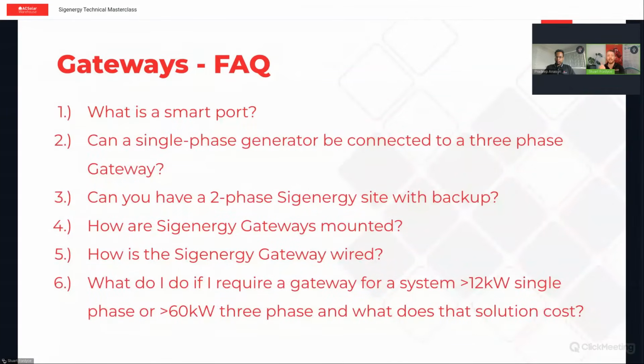So the smart port is a contactor and a breaker in line. So the system can completely isolate, or open and close, this contactor to engage or disengage that breaker. And there's a breaker in both the single phase and the 3-phase gateway that allows you to put either a generator, a third-party solar system, or a smart load of some sort. And that load might be something that the homeowner wants the ability to switch on and off for whatever reason. But it also might be a load that you use to shed energy, like a pool pump. And that's what you put through that smart load. But there's only one smart port in each of the gateways. So if you're doing an off-grid system with a generator or a third-party solar system, you'll have to pick one or the other to engage it in a smart way.